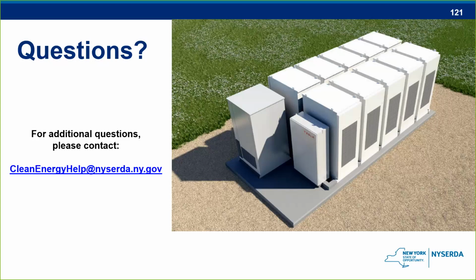Let's see. Yeah, so do we have thoughts on the use of gas detection as a way of stopping thermal runaway early on, for lithium-ion? Any extra layer of protection reduces risk, so I don't have any bad thoughts to say about it, but anytime you add another layer of protection, you reduce the risk of an event taking place.